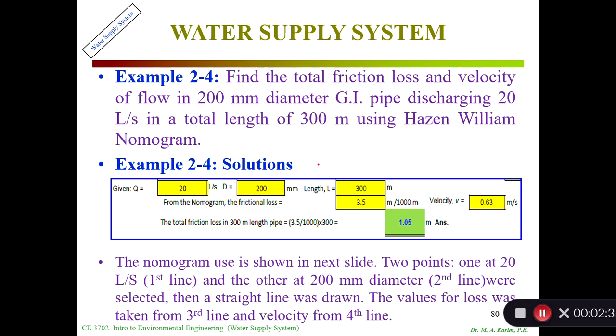Now we'll solve Example 2-4. Find the total friction loss and velocity of flow in a 200 millimeter diameter GI pipe, galvanized iron pipe, discharging 20 liters per second in a total length of 300 meters using Hazen-William Nomogram. The Hazen-William Nomogram is the older method; people used to use it. It has an equation and a nomogram.